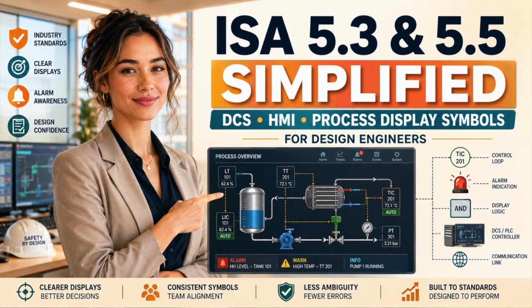Site testing must consider normal viewing distance, control room lighting, multiple monitors, alarm banners, fatigue, and the pressure of real operation. The final question is not whether the display looks modern. The final question is whether the operator can understand the truth immediately. When the plant is stable, almost any display appears acceptable. The true quality of the design emerges when the transmitter fails, the compressor trips, the controller saturates, the valve sticks, the communication link disappears, or the sequence stops halfway.